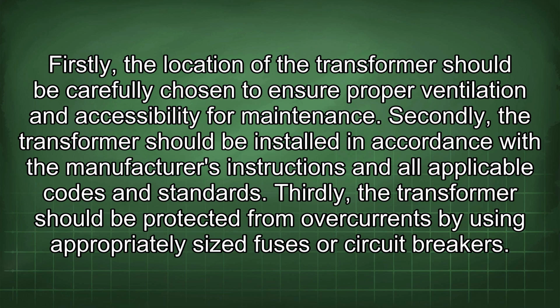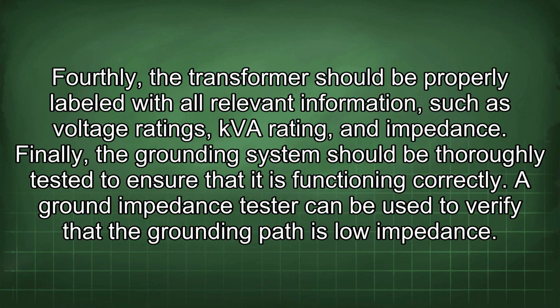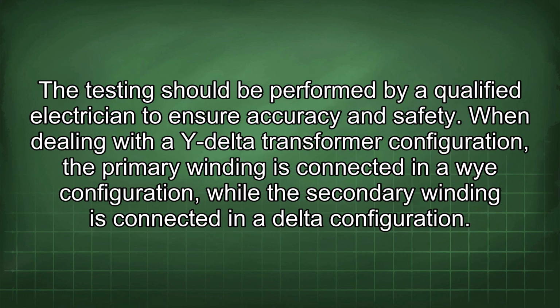Thirdly, the transformer should be protected from overcurrents by using appropriately sized fuses or circuit breakers. Fourthly, the transformer should be properly labeled with all relevant information, such as voltage ratings, kVA rating, and impedance. Finally, the grounding system should be thoroughly tested to ensure that it is functioning correctly. A ground impedance tester can be used to verify that the grounding path is low impedance. The testing should be performed by a qualified electrician to ensure accuracy and safety.